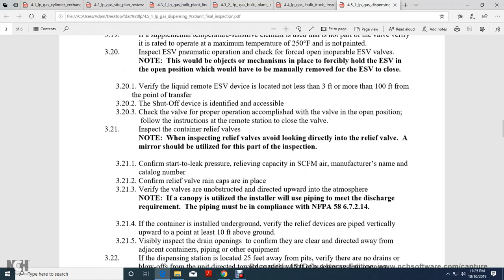Verify liquid withdrawal and remote emergency shutoff valve is located not less than 3 feet but not more than 100 feet from the point of transfer. The shutoff device is identified and accessible. Check the valve for proper operation, accomplished by placing the valve in the open position, then from the remote station, close the valve and inspect the container relief valves.